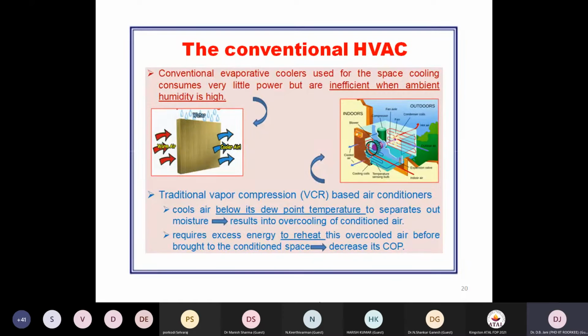For a layman, refrigeration and air conditioning means temperature, but typical air conditioning applications also need to maintain humidity, and that humidity must be within 50%. If humidity is greater, it should be reduced, and if humidity is lower, it should be increased. For a particular season, slight variations are allowed from 45 to 55%.